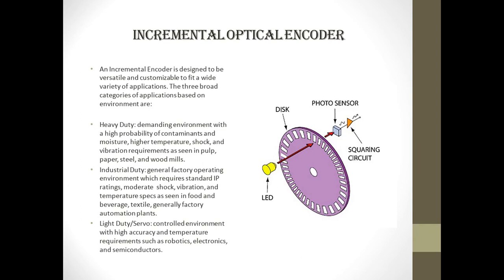Information about velocity is available by looking at the time interval between the pulses or at the number of pulses within a time period. As for example, if we divide a shaft rotation into 1000 parts, an encoder would be selected to supply 1000 square wave cycles per revolution. By using a counter to count these cycles, we can find how much the shaft has rotated. Suppose the count is 100, then the shaft has rotated only 36 degrees.